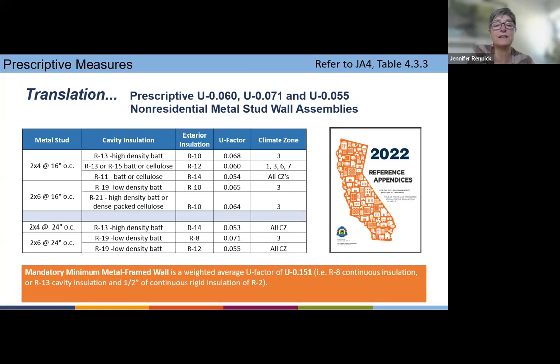For example, in climate zone 3, which is a milder climate zone, you could use a 2x4 metal stud wall with R13 batt insulation in the cavity and R10 exterior insulation, giving you a U factor of 0.068. That's better than the required 0.071, so it works for climate zone 3.